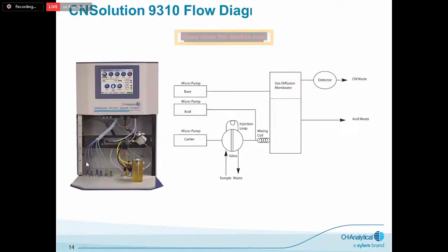This shows the inside of the CN9310. One comment about this picture, it's a little bit older picture. The newer instruments have a peristaltic pump that sits here now, as opposed to the diaphragm pump that's on this valve manifold here. That's the only difference. What you see down below are 1, 2, 3, 4 sample stream ports that are available, and these two would be used for calibration. This is the valve manifold, which injects the various chemicals such as the base, the acid, and the carrier. Up here is where the sample loop, or the valve with the sample loop, is located. And down here is the gas diffusion membrane. We have the base that comes across the top of the manifold, the acid and sample mixture, which comes to the bottom.